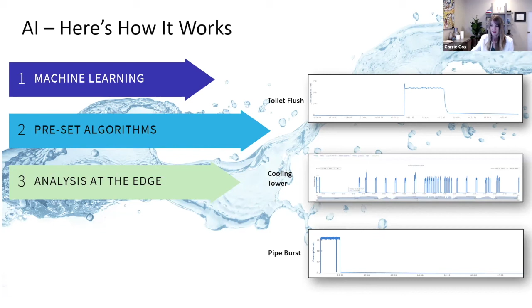At a high level, we combine machine learning with our preset algorithms, and together those provide analysis at the edge. When I say at the edge, every single device and system should have the ability to monitor its individual area separately. So, for example, if you've got a cold water riser or a group of risers, that individual system should only be monitoring that area, and therefore should only be able to shut down water in that area. What you'll see here on the right are examples of specific water patterns that a system sees in order to make those decisions.